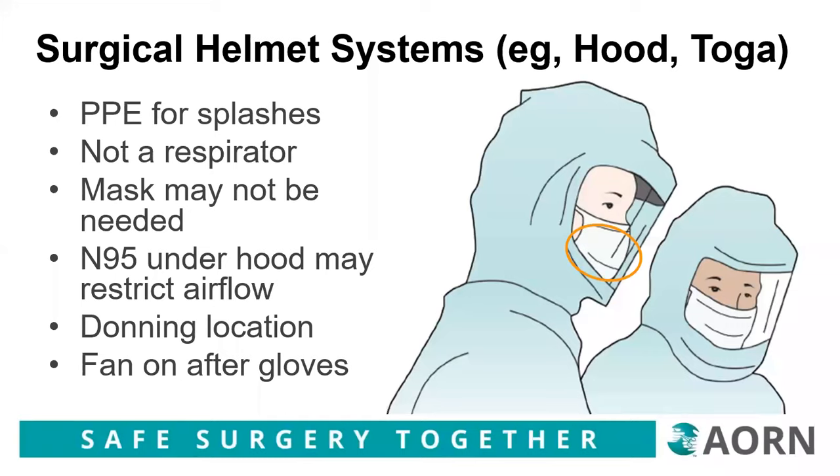Four questions were asked about the use of hoods when caring for COVID-19 patients, and it can be easy to confuse PAPRs and surgical helmet systems because they look similar. Surgical helmet systems, commonly referred to as hoods and togas, are typically worn in orthopedic procedures, and are a type of PPE that protects personnel from splash, splatters, or sprays. But these devices are not certified for respiratory protection. Conversely, PAPRs are certified as respiratory protection from airborne disease.